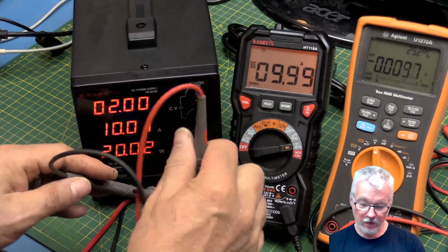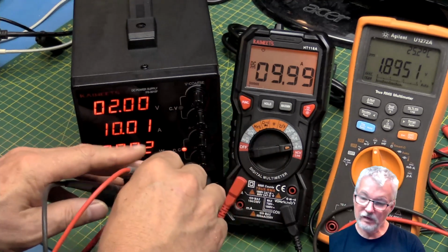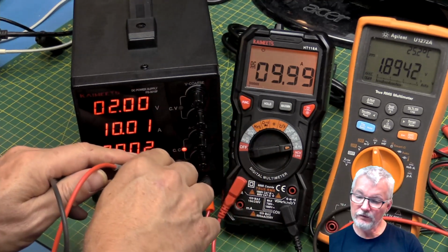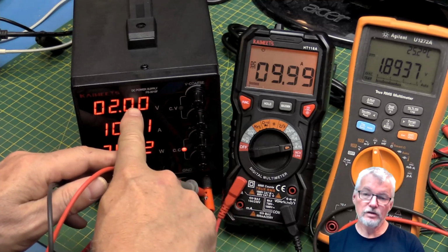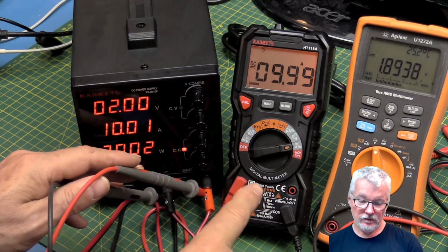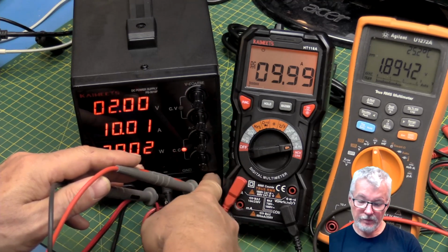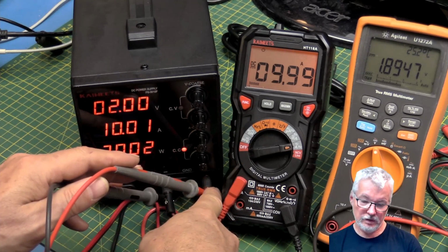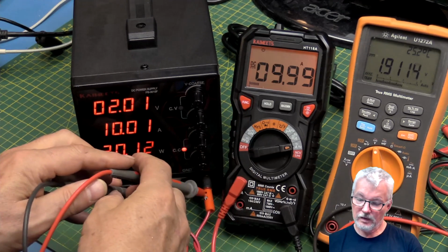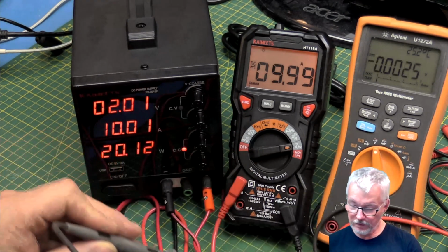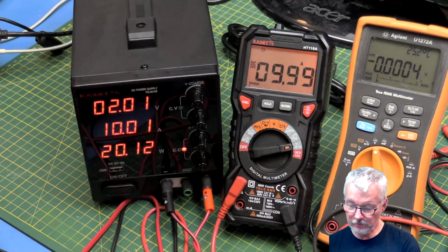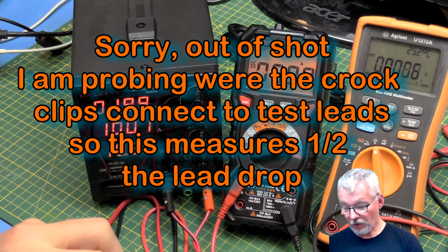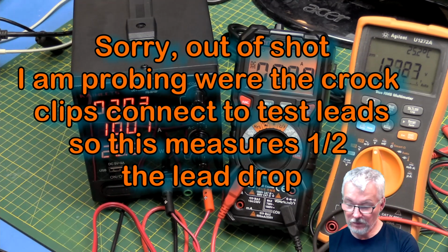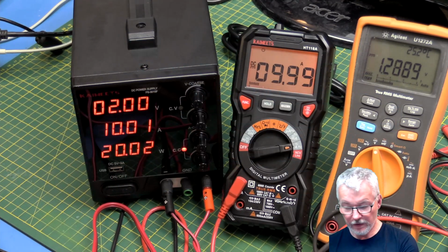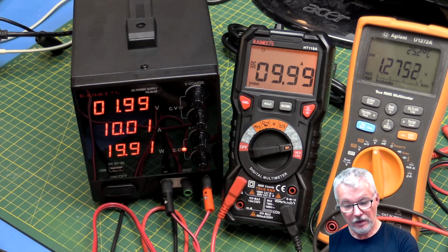I can feel all these wires getting quite toasty. Right, 1.89 volts here. This is reading 2 on the front panel. So we're already dropping a little bit, probably in the cabling coming out of here from where this is measuring. And if we come over here and measure at the probe, so we've got the first piece of wire here, right? So you can see what I'm saying about the wires being inadequate at 10 amps.